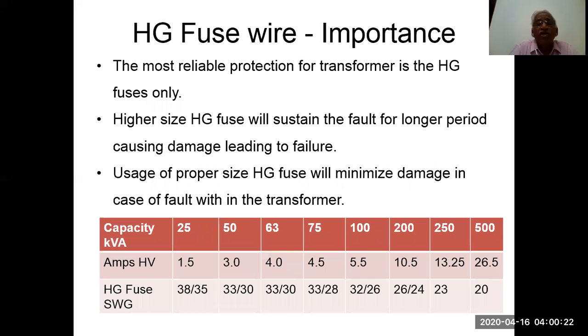HG fuse and wire importance. This is what we use on the HT side of the 11 kV transformers up to something like 500 kVA. A higher size HG fuse will sustain the fault for a longer period, causing damage leading to failure. Using the proper size of HG fuse will minimize the damage and the cause of the fault in the transformer. A table is given here with capacities and amperes mentioned on it. HG fuse size and standard wire gauge are also mentioned.